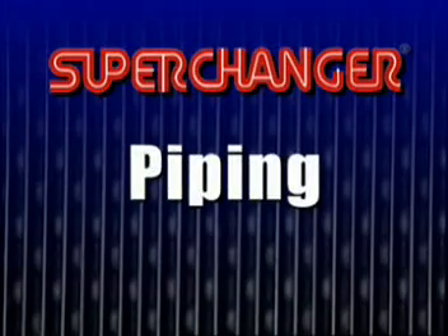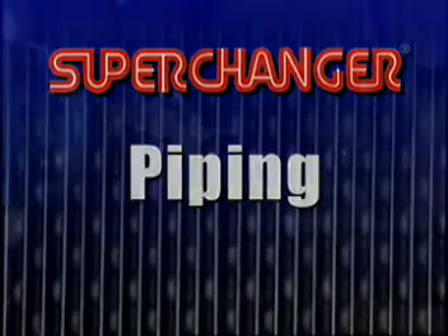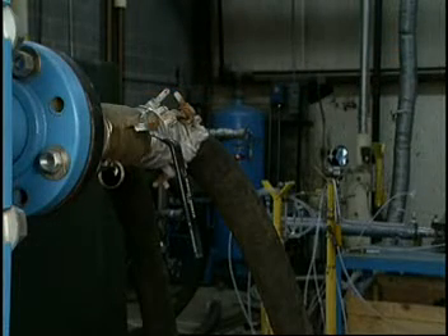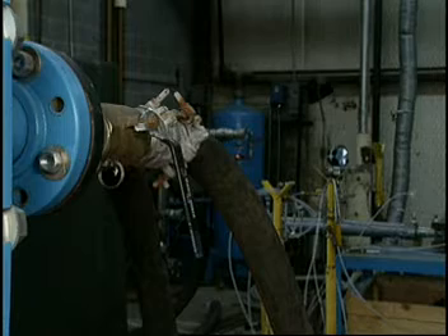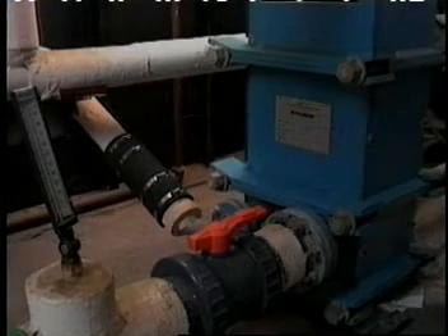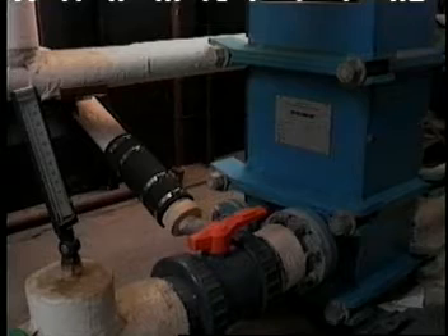All piping connected to the Superchanger unit should be properly supported as close to the heat exchanger as possible. If required, a flexible connection should be made to the exchanger. This will isolate the exchanger from any thermal expansion or vibration in the piping systems.